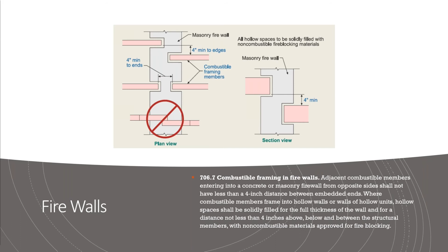Where combustible members frame into hollow walls or walls of hollow units, those hollow spaces shall be solidly filled for the full thickness of the wall and for a distance not less than 4 inches above, below, and in between the structural members with non-combustible materials approved for fire blocking. So very specific when you've got combustible construction, which makes sense. What has to happen when these members are embedded into this firewall? So specific requirements for that. And again, the visual to help out with what's okay, what's not okay, and what do these words even mean? Here's what it looks like.